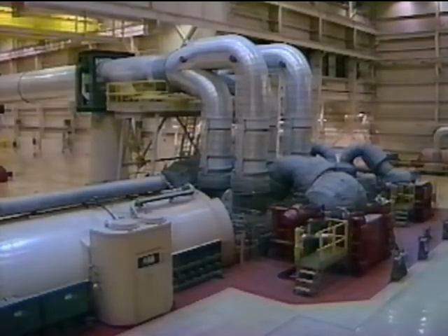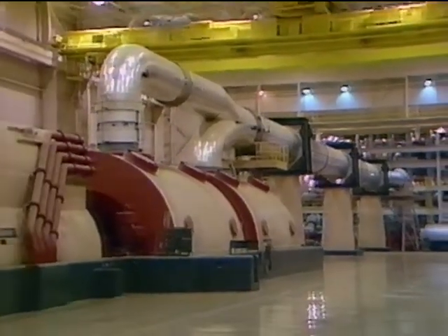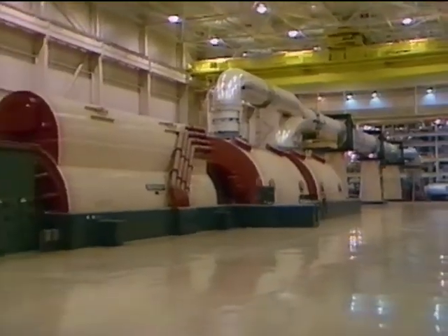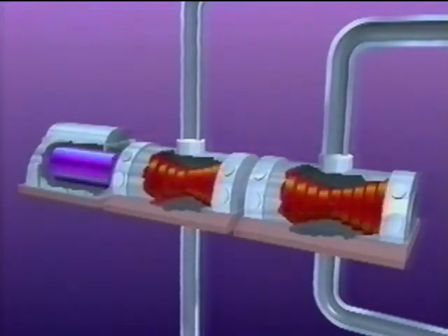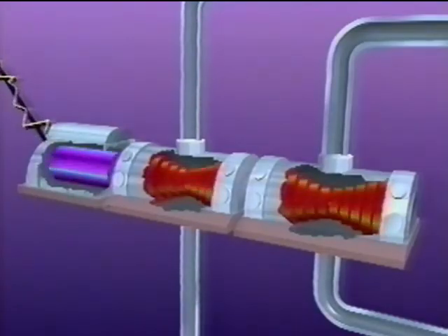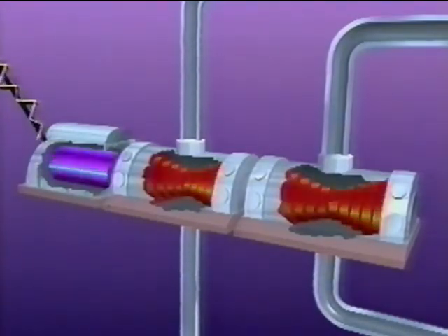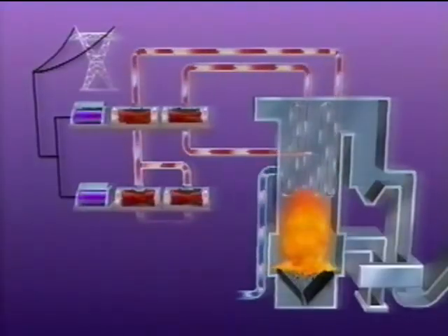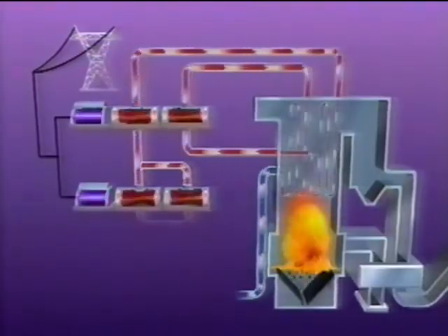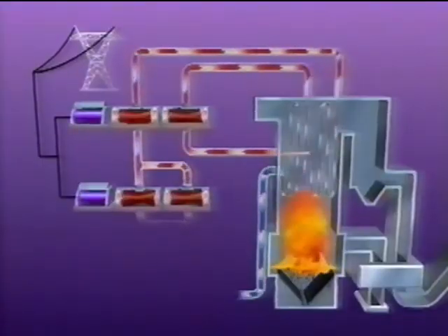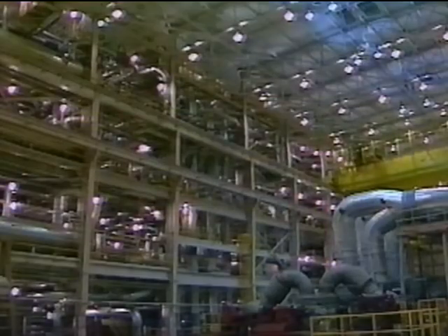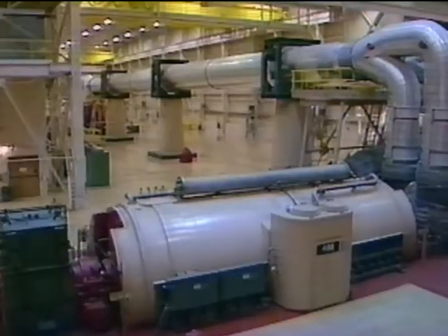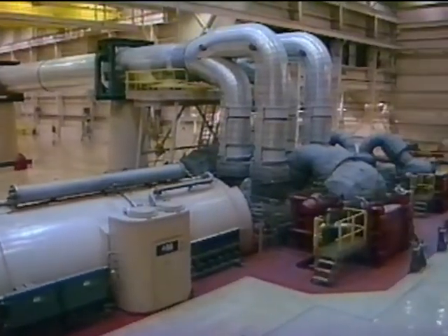First, the steam pressure drives the high pressure and intermediate pressure, or reheat, turbines. Next, exhaust steam is used to spin low pressure turbines. The steam-driven turbines then drive the generators. This high-pressure, high-temperature steam cycle process at Zimmer, known as a supercritical cycle, makes Zimmer's steam cycle more efficient than standard superheated steam boiler cycles. At full capacity, Zimmer is capable of producing 1,300 net megawatts of electrical power.